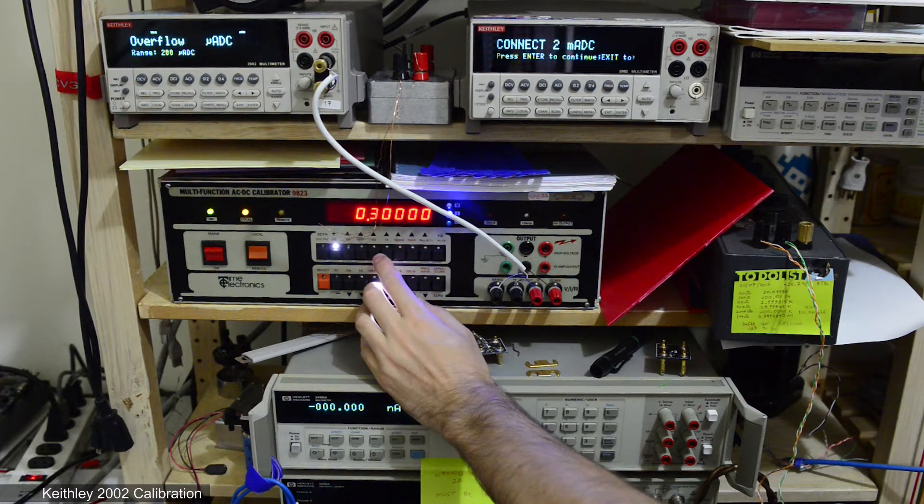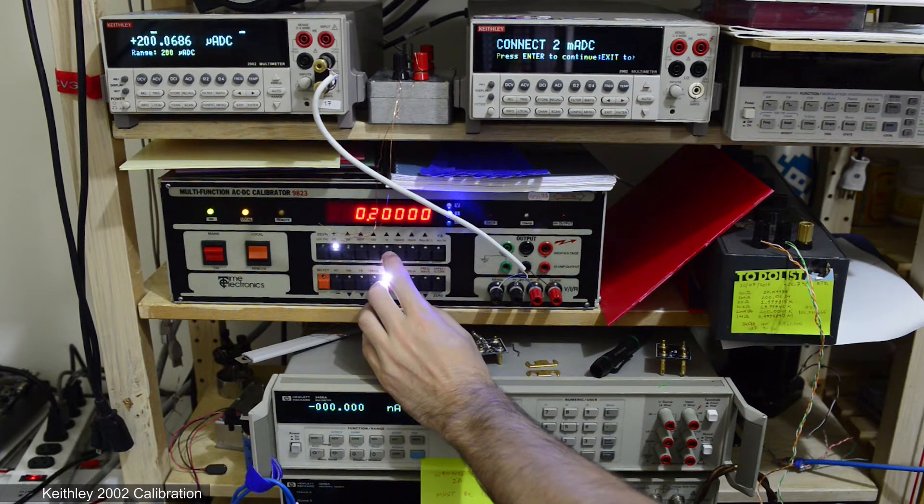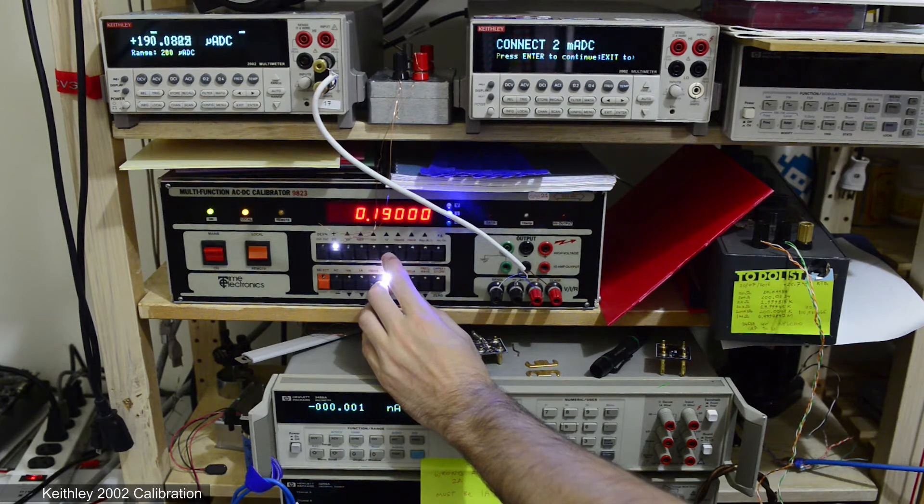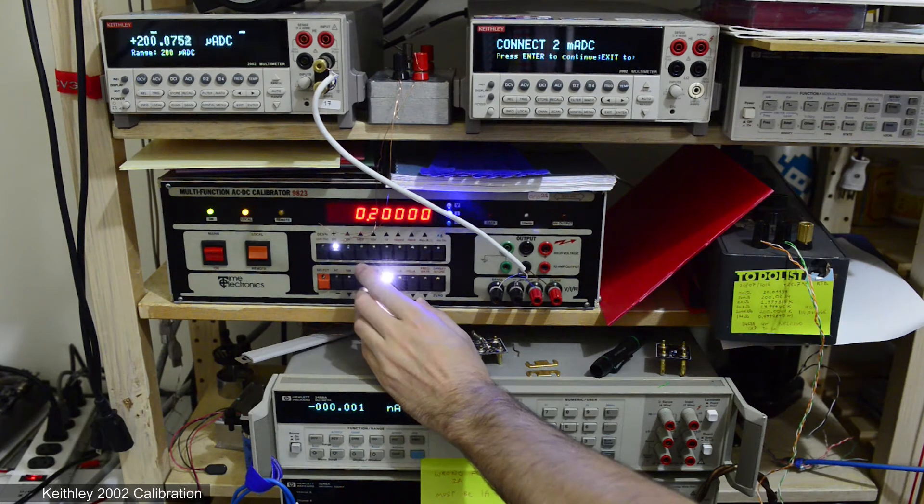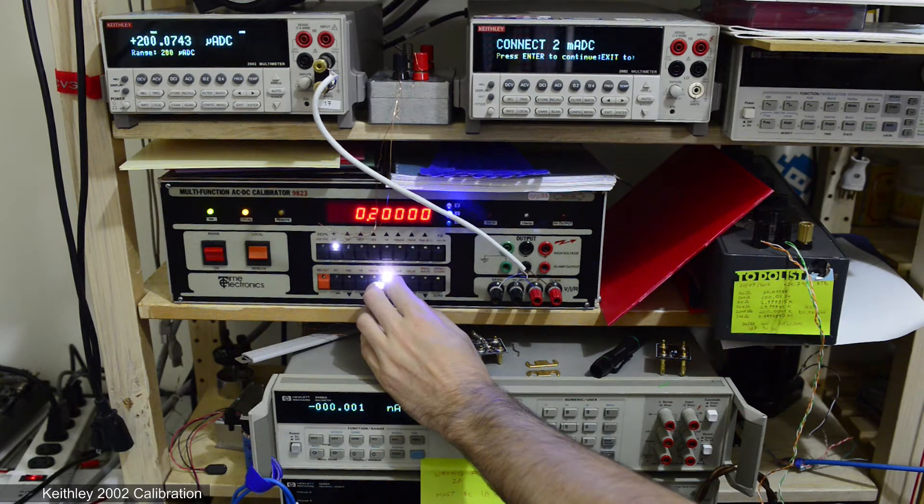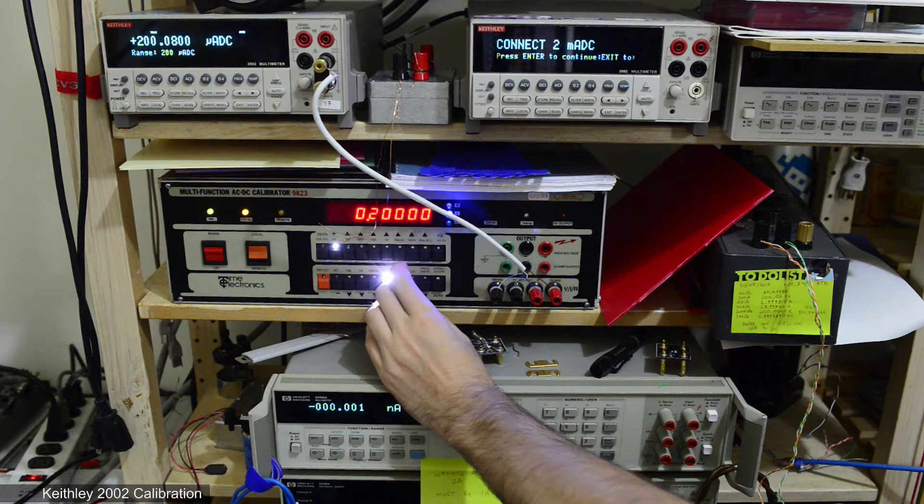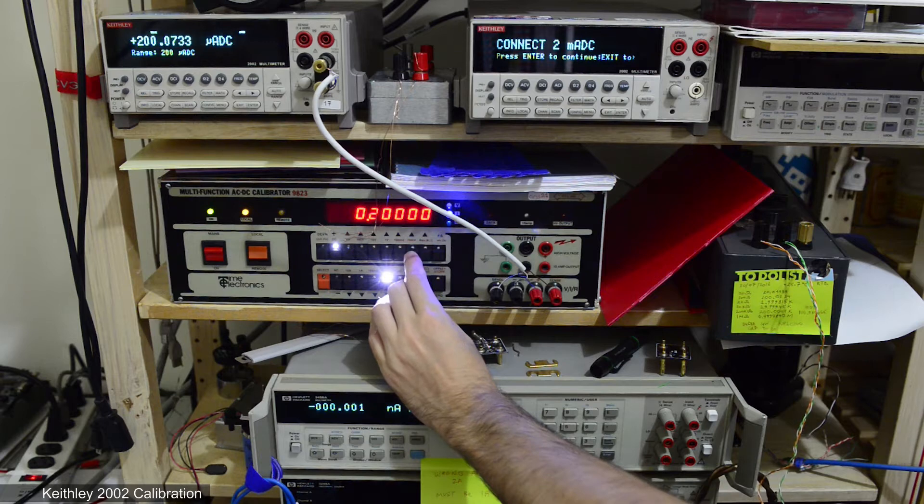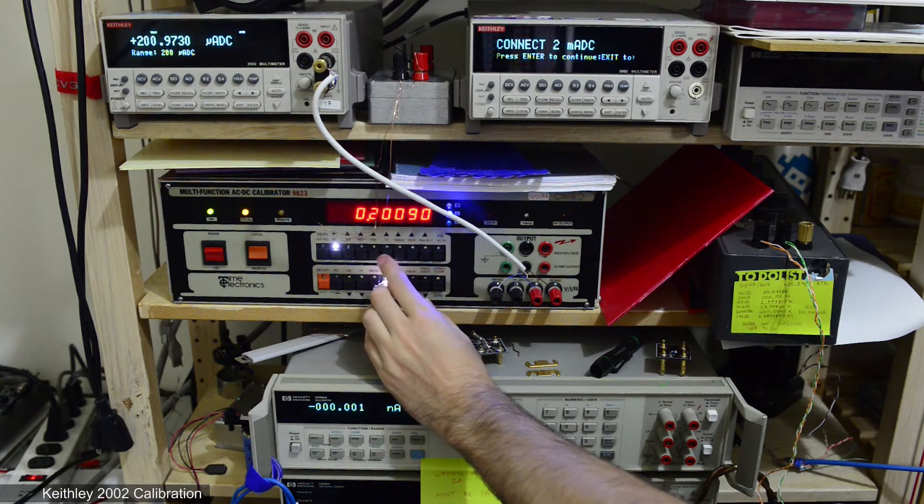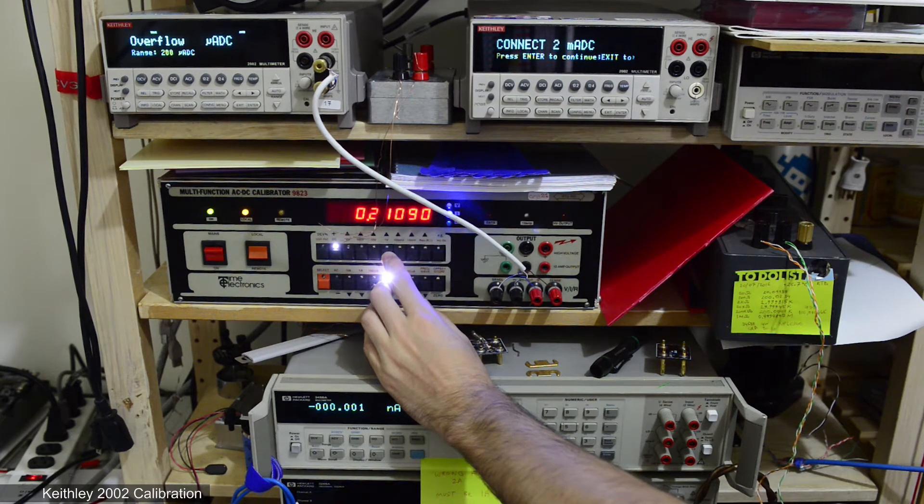Now same test with 20 milliamp current range on calibrator and 200 microamps output fine. So I will have to use 20 milliamp current range on the calibrator with reduced resolution to calibrate this tricky 200 microamp range.